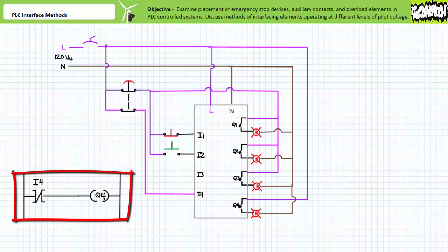The inclusion of this single line in the PLC program would serve this purpose. A break instruction examining input 4 energizes and de-energizes output Q4. When the e-stop is in the deactivated closed condition, input 4 experiences a logical 1, and the break instruction examining input I4 does not permit logical continuity onto output Q4. Output Q4 is not energized, and the fourth pilot lamp is dark.